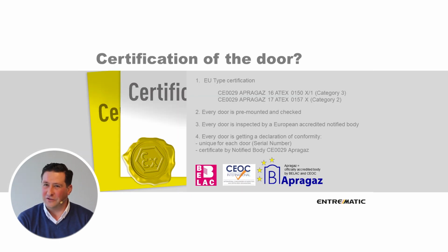The certification of the door. Every door is receiving a complete certification. We have 2 type certifications, one for category 3 and one for category 2. In practice, every single door is pre-mounted at our facilities and is inspected and checked by the European notified body, in this case Apragaz. The certificate is on the serial number of the door. So this means that each serial number is receiving a unique certificate.